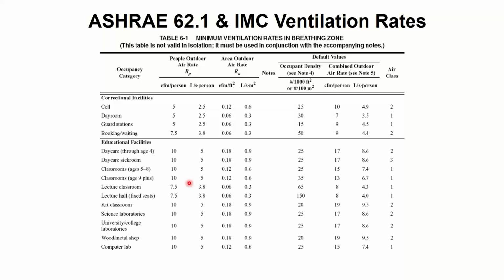Many of the codes adopt ASHRAE Standard 62 directly, or they cut and paste like 90% of it and put it in their code. So the IMC, which is the International Mechanical Code, has the exact same tables as ASHRAE 62.1. ASHRAE 62.1 gets updated every 3 years. IMC gets updated every 3 years. They do it 18 months after ASHRAE.